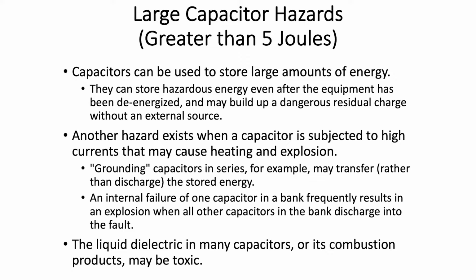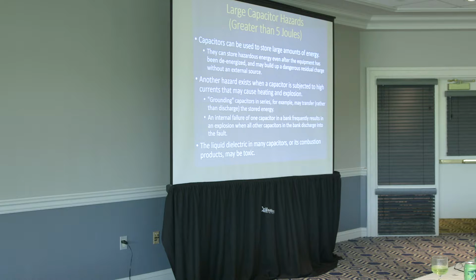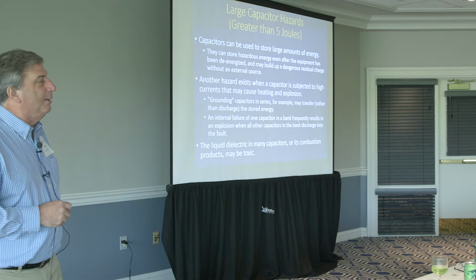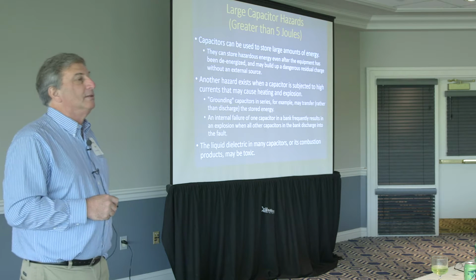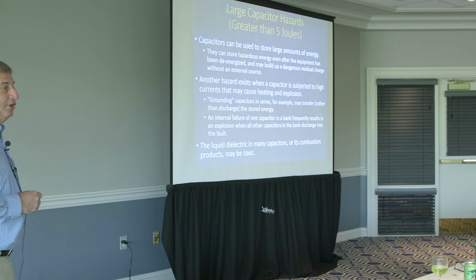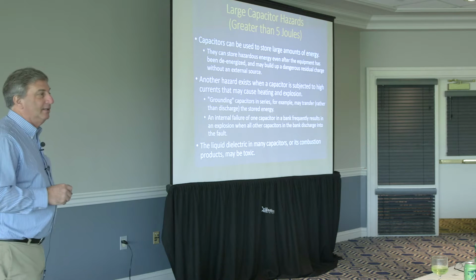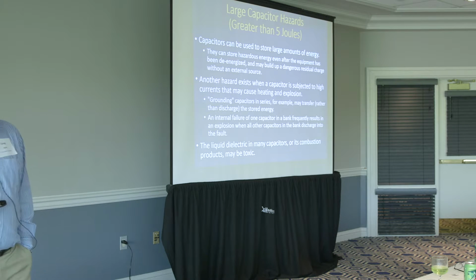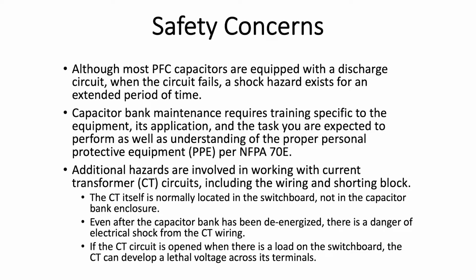An internal failure of one cap in a bank frequently results in an explosion when all the other capacitors in the bank discharge into the fault. The liquid dielectric in many capacitors or its combustion products can be toxic. So even if the shrapnel didn't get me when I was in the room, the fumes could still cause some damage to me in terms of now I was in the wrong place at the wrong time.